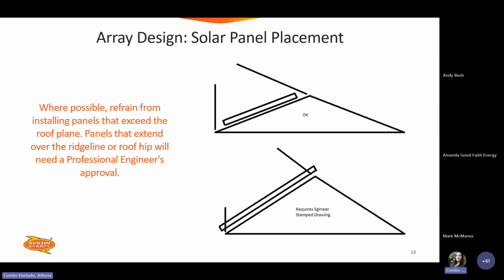Okay, array design, solar panel placement. When possible, please make sure that you are in the roof plane. Any arrays that exceed the ridge line or go over the roof hip will need a PE stamp, so you'll have to have the engineer's drawings on those stamps. The top where you're in plane, and then on the bottom where you're over, you're just going to need those stamps. It's just an extra step, and just make sure, if that's the case, that you're going through and getting those stamps.